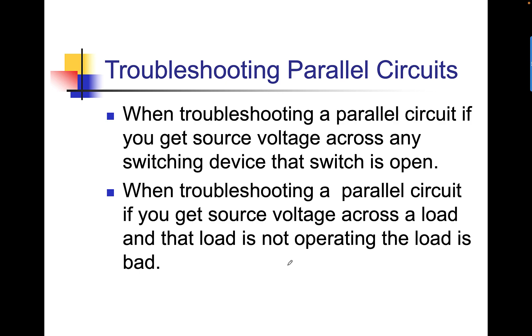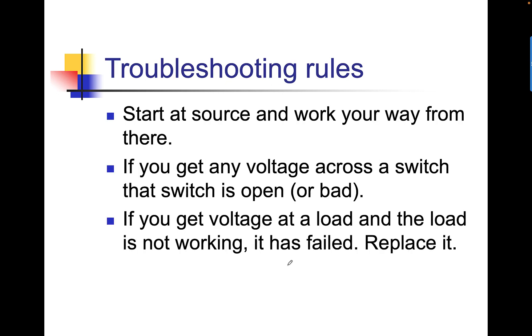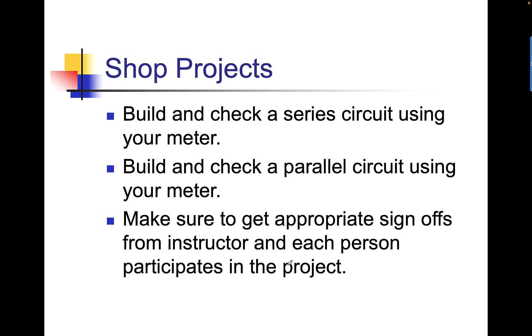When troubleshooting a parallel circuit, if you get source voltage across any switching device, that switch is open. When troubleshooting a parallel circuit, if you get source voltage across a load and the load is not operating, the load is bad. Don't overanalyze it. If you get 240 volts or source voltage across a load and the load is not operating, the load is bad. Start at the source and work your way from there. Use the hopscotch method. Put one of your meter leads at source. Leave it there. If you get any voltage across a switch, it's open or sometimes bad. If you get voltage across a load and the load is not working, it has failed. Replace it.